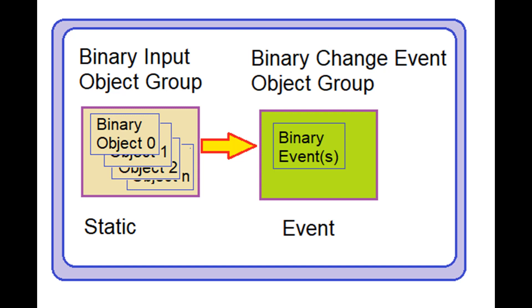There are two object groups for each input point type: static and event. A static object group contains the current value or state of each point plus its set of flags. An event object group contains a list of events declared on members of the associated static object group; each entry contains the static value as it existed when the event was declared, and may additionally include the time of occurrence. A master can ask for the current state of points by reading the static object group, or ask for events by reading the event object group, which only contains unreported events.